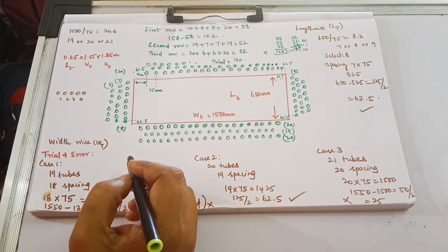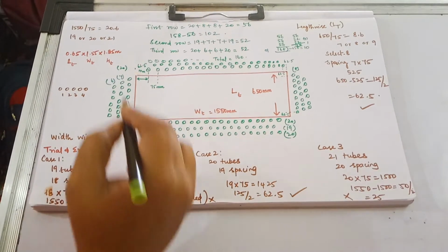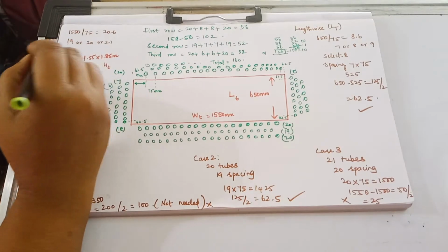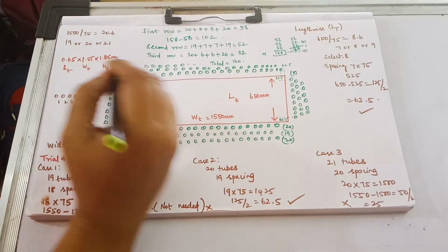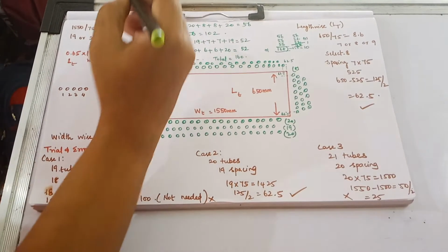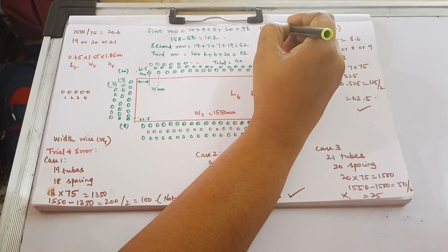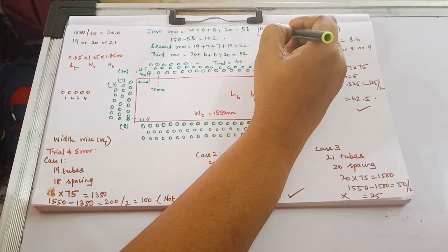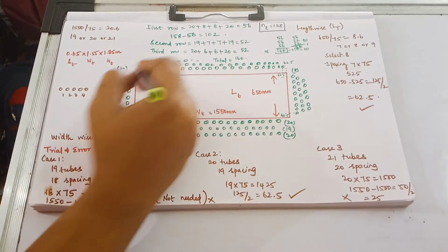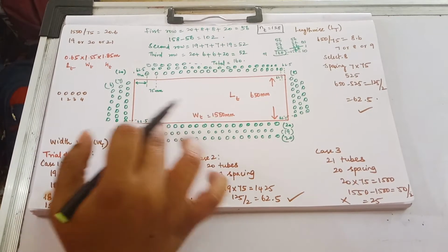In this video, we are going to discuss how we are going to place the number of tubes outside of the transformer. In the previous problem, we calculated the number of tubes NT is equal to 158. Now we have to place these 158 tubes in the transformer tank, so they should be available outside the transformer tank.